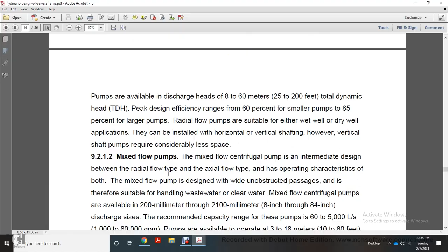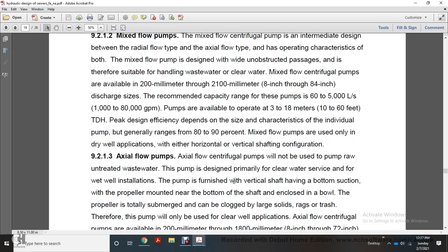Mixed flow pumps. Mixed flow centrifugal pumps, intermediate design, medium between radial flow type and the axial flow type of the operating characteristic of both. The mixed flow pump is designed with wide unobstructed passages and is therefore suitable for handling clear water. Mixed flow centrifugal pumps are available in 8-inch to 84-inch discharge size. Recommended capacity ranges between 60 to 5,000 liters or 1,000 to 80,000 gallons per minute. Pumps are available to 3 to 18 meters or 10 to 60 feet of total dynamic head. Peak design efficiency depends on the size and characteristics of the individual pump, but generally ranges from 80 to 90%. Mixed flow pumps are used only in dry well applications in either horizontal or vertical shaft configuration.